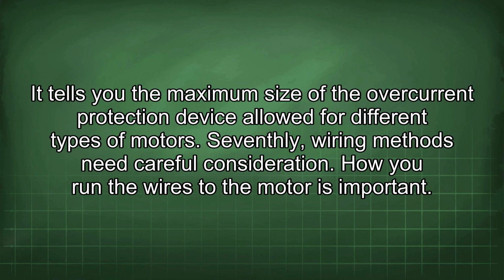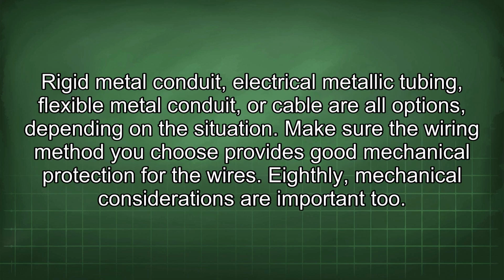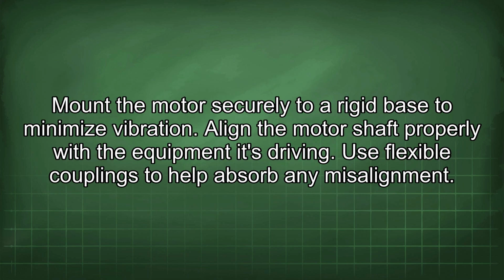Seventhly, wiring methods need careful consideration. How you run the wires to the motor is important. Rigid metal conduit, electrical metallic tubing, flexible metal conduit, or cable are all options depending on the situation. Make sure the wiring method you choose provides good mechanical protection for the wires. Eighthly, mechanical considerations are important too. Mount the motor securely to a rigid base to minimize vibration. Align the motor shaft properly with the equipment it's driving. Use flexible couplings to help absorb any misalignment.